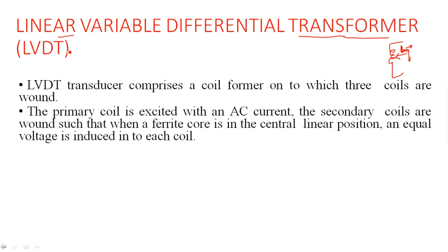The LVDT transducer comprises a coil former onto which three coils are wound. The primary coil is excited with an AC current. There are two secondary coils — primary is a single coil and secondary has two coils. These secondary coils are wound such that when a ferrite core is in the central linear position, equal voltage is induced into each coil.